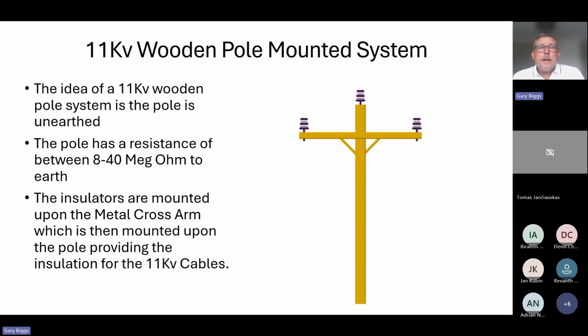itself is unearthed. Now the pole has a resistance to ground from the cross arm that you can see at the top here. Hopefully you can all see my indicator there showing that cross member, but you'll have a metal cross member that will be attached to the wooden pole, and then the system itself, the 11 kV cabling, will be mounted on top of the insulators which carry it from A to B. The whole idea of this system is the pole itself will be somewhere between 8 and 40 megaohms. So that means if an insulator partially breaks down, the system can hold up and still be live and still be useful to us, as in carrying our electricity.